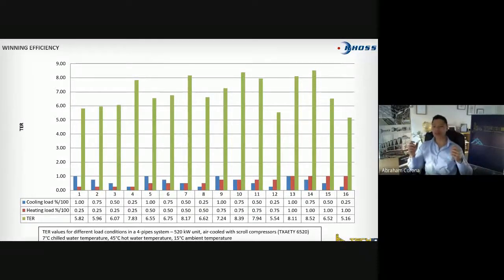But in my opinion, COP is only one point of the graph. And normally when you're selecting a COP, say I'm selecting this COP at design condition, in order to minimize the cost of the unit, you basically define that COP at your maximum working load, or very close. That means that at that moment, that chiller, that heat pump is working at, let's say, 100% capacity. That means that your inverter is doing nothing. You can give a good COP at more or less the same level without an inverter compressor.